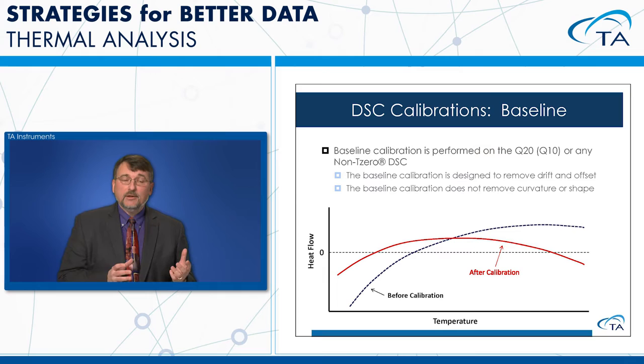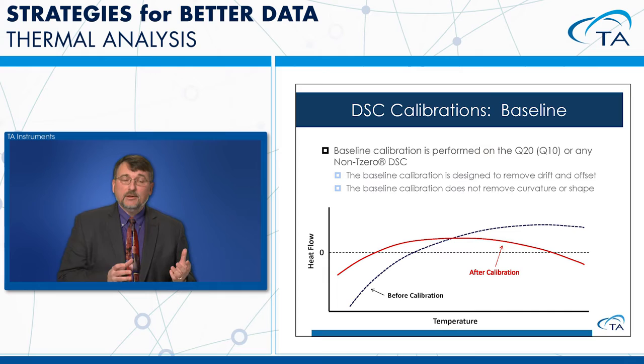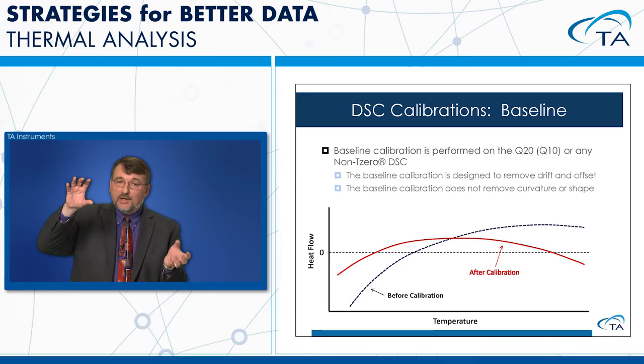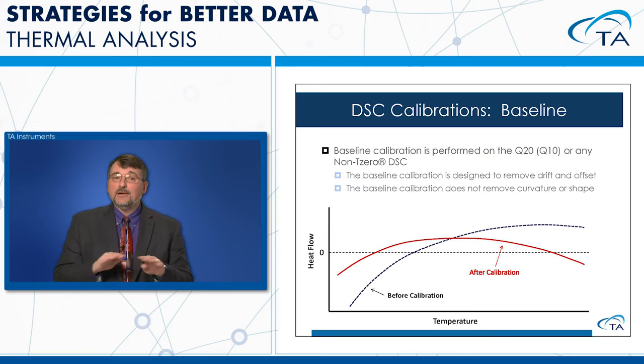The baseline calibration done on non-T0 DSCs like the Q20 corrects for any offset and drift in the baseline. Looking at the graph, the black curve is our before-calibration data. We rotate it around zero to get our calibrated baseline — it still has some curvature, but it's now relatively flat and right around zero.